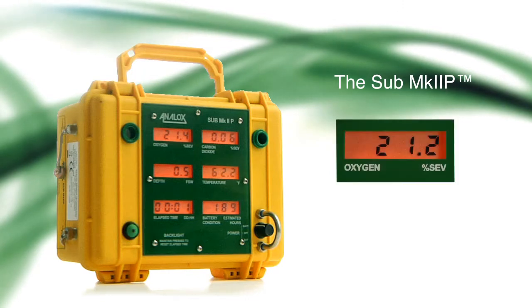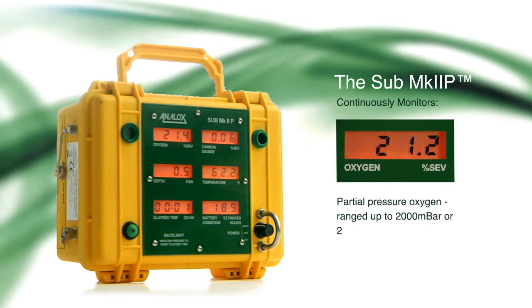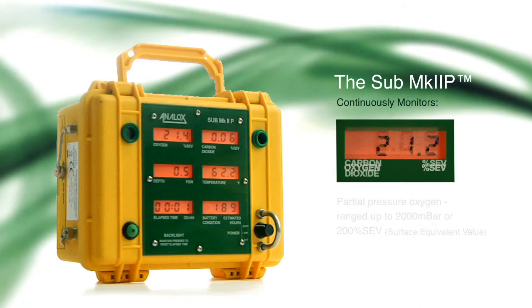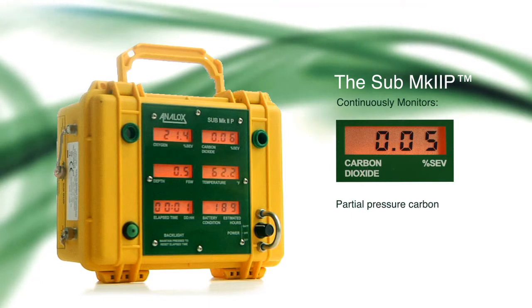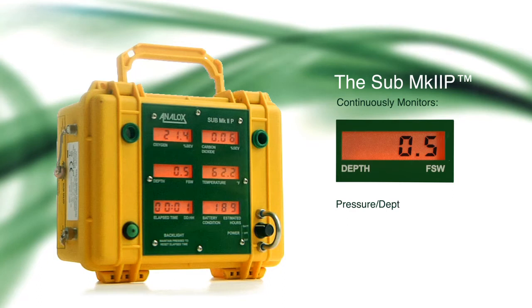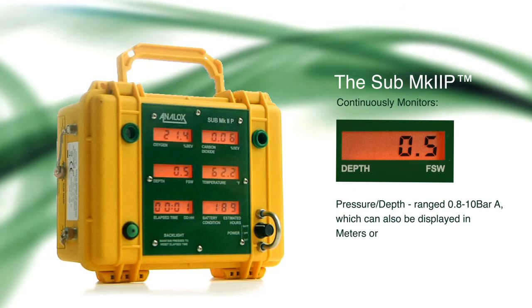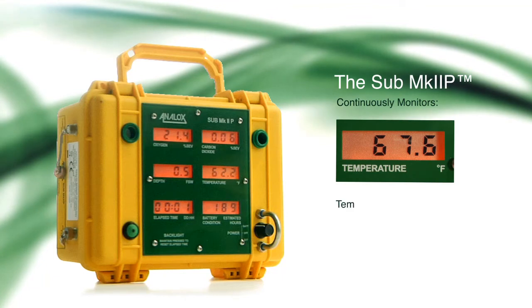The Sub-MkIIP continuously monitors partial pressure oxygen, ranged up to 2000 millibar or 200% SEV, surface equivalent value. Partial pressure carbon dioxide, ranged up to 100 millibar or 10% SEV, surface equivalent value. Pressure, ranged from 0.8 to 10 bar absolute, which can also be displayed in meters or feet of seawater. Temperature, ranged from 0 to 40 degrees Celsius, 32 to 104 Fahrenheit.